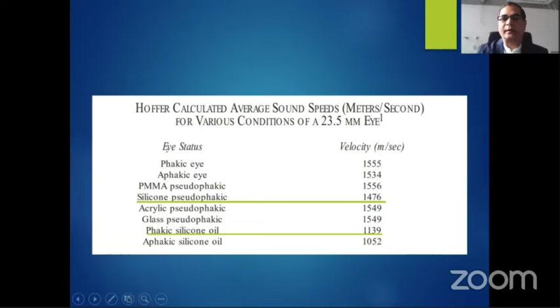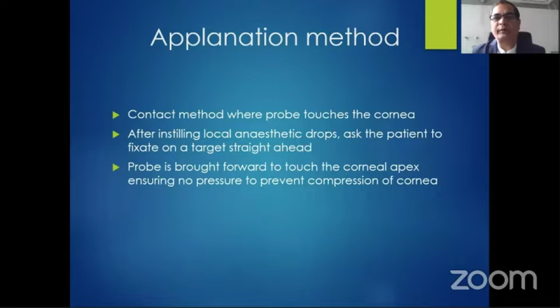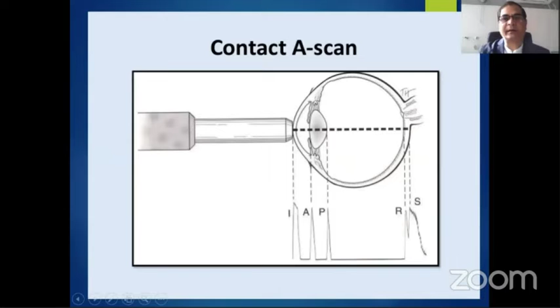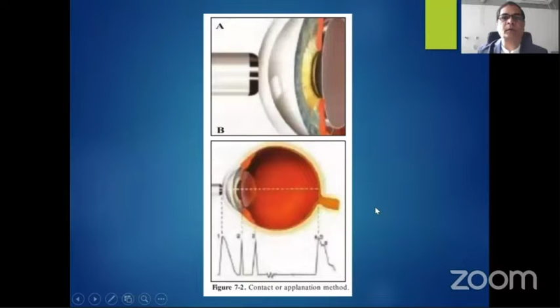Applanation method is a contact method where the probe touches the cornea. After instilling local anesthetic drops, ask the patient to fix at a target straight ahead. The probe is brought forward to touch the corneal apex, ensuring no pressure to prevent corneal compression. This is the schematic diagram, and you can see the probe is just touching the cornea. It is not pressing, and the beam is going and coming back, and at every tissue interface it is giving a spike.